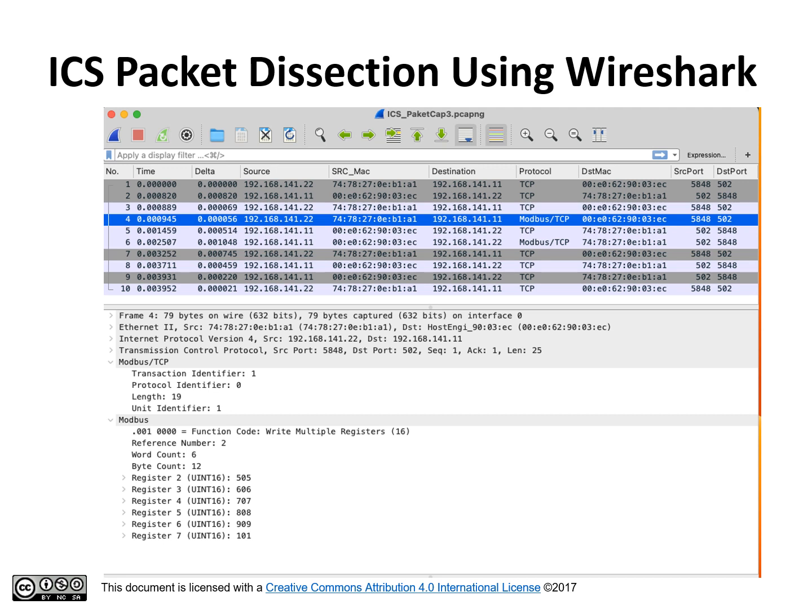Refer to the Modbus TCP ADU slide to understand the Modbus TCP segment of the packet. The Modbus segment contains the function code; value 16 indicates write multiple registers. The word count is equal to 6, indicating 6 values will be written to the output registers of the PLC. The values written, starting at register 2 up to register 7, are shown.